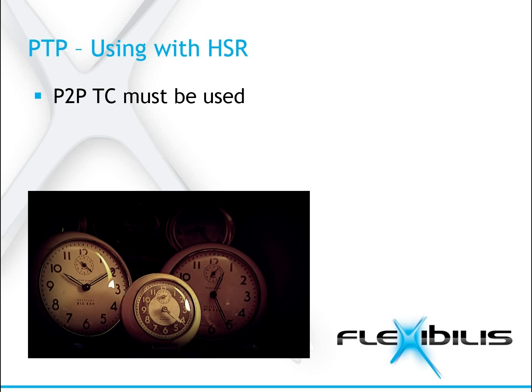This means that one-step clock must be used with HSR. FRS supports one-step transparent clock, which means it makes its correction to the event message, not the follow-up message. Because one-step transparent clocks are compatible with two-step operation, FRS can be used as a transparent clock also in networks that use two-step clock.